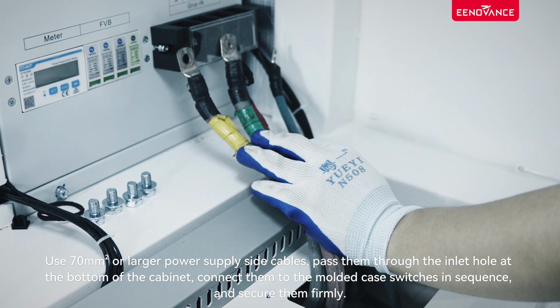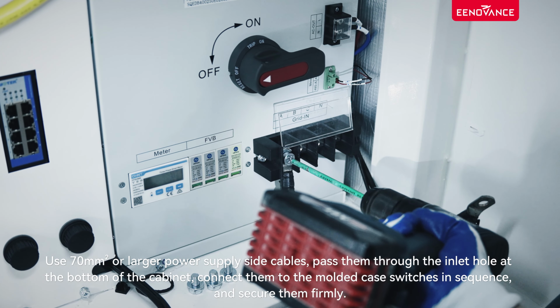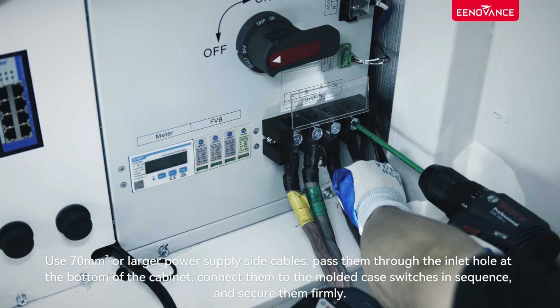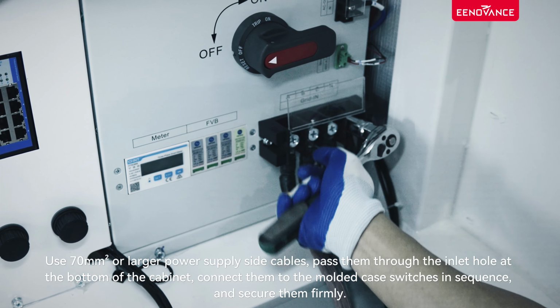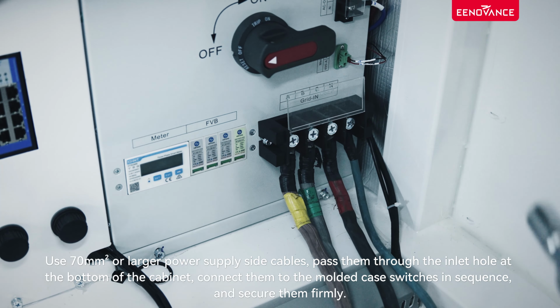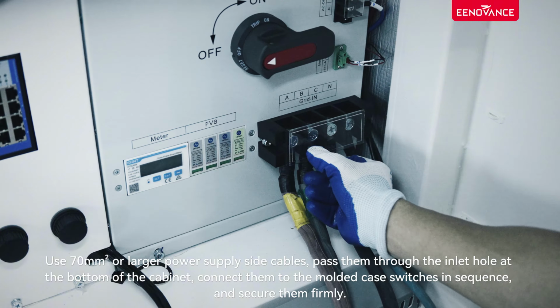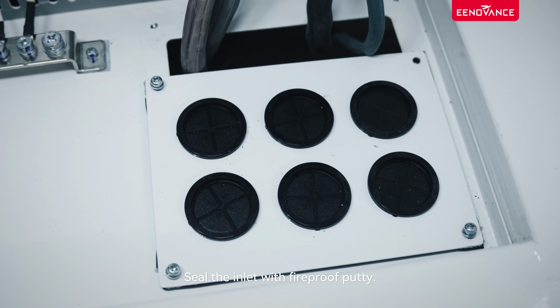Use 70 square millimeters or larger power supply side cables. Pass them through the inlet hole at the bottom of the cabinet. Connect them to the molded case switches in sequence, and secure them firmly. Seal the inlet with fireproof putty.